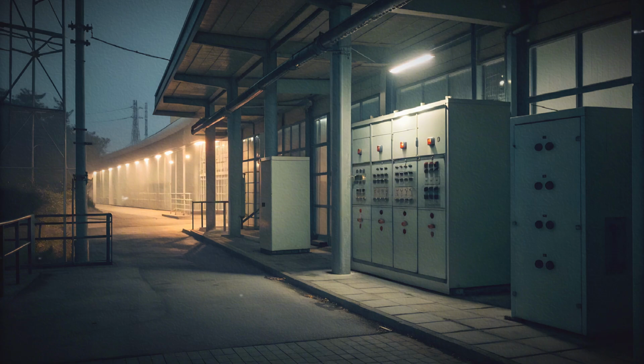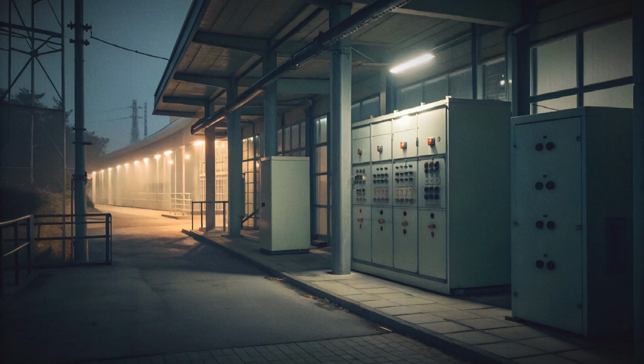If a breaker fails to interrupt a fault when instructed, associated protection detects the failure and initiates alternative actions. These actions may include tripping adjacent breakers or opening breakers at both ends of a line. The goal is to remove the fault from the network, even if a single breaker does not operate as intended.